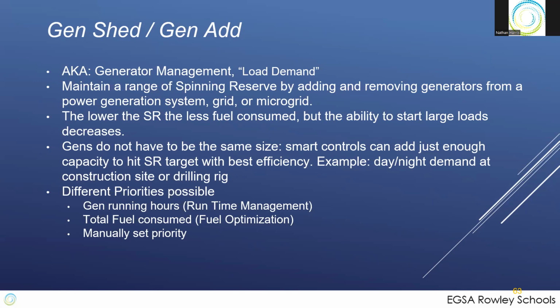They don't necessarily have to be the same size anymore. At one time, we always said, make sure your gens are the same generator, same size, in parallel, because that's when they're analog load share. Now that the digital stuff is here, that's not necessary, you can run different size units in parallel with each other just fine. Watch your winding pitch, of course, we talked about that yesterday, but the actual size doesn't matter that much.